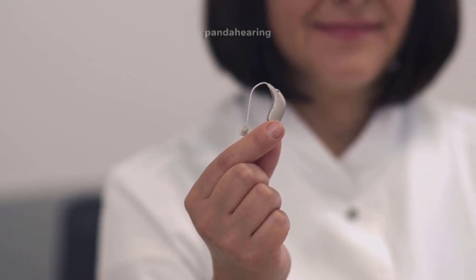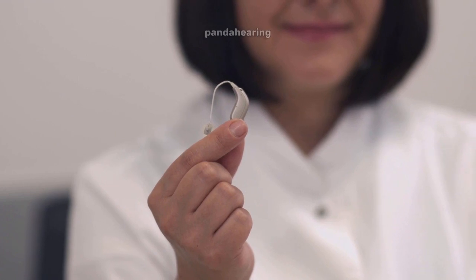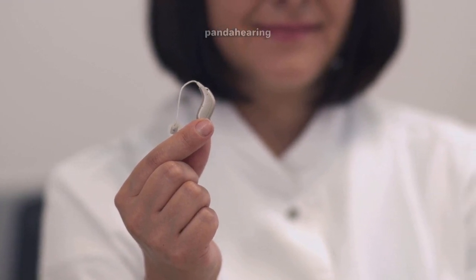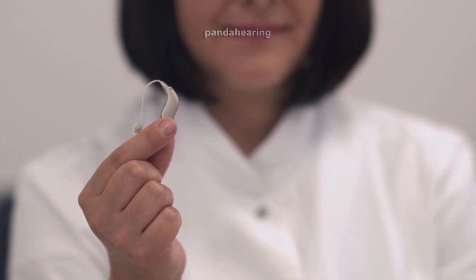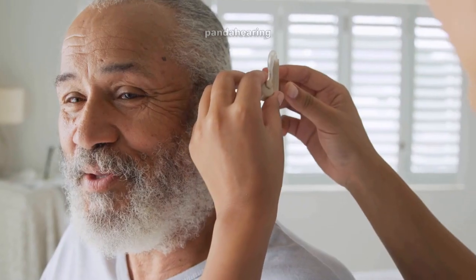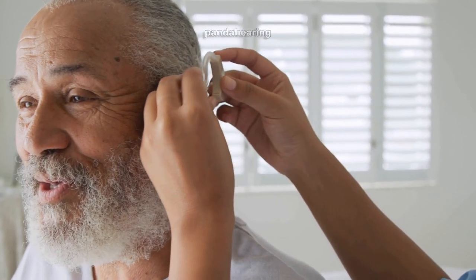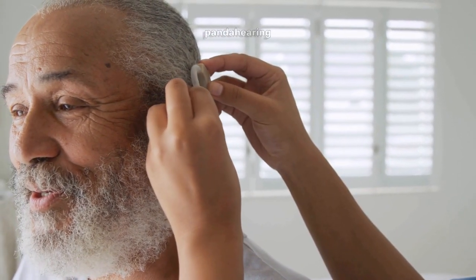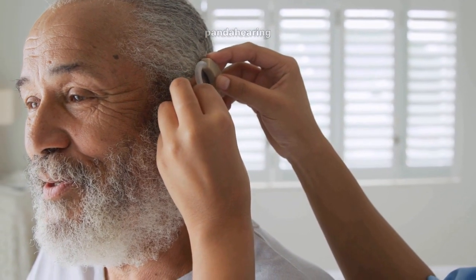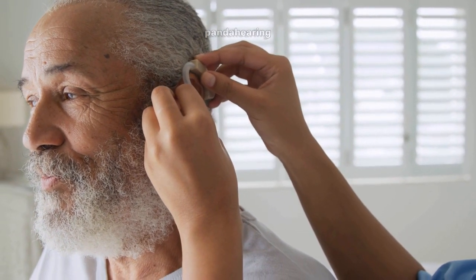What is meant by the term hearing aid feedback? Hearing aid feedback occurs when sound that is produced by the hearing aid speaker and then released into the surrounding environment is picked up by the hearing aid microphone. This loop results in a sound that is similar to whistling or screeching. Hearing aids are designed to reduce the likelihood of feedback as much as possible, yet there are circumstances and kinds of hearing aids in which feedback can still occur.